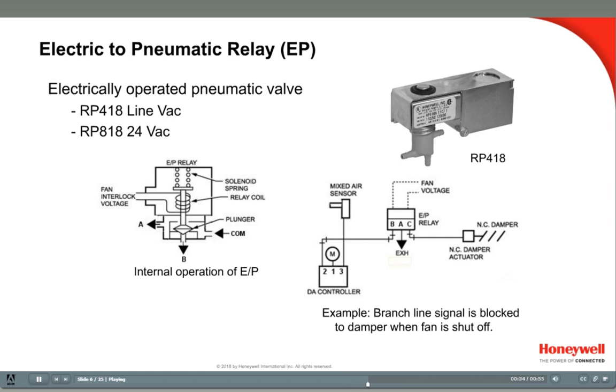The EP relay might be wired to a fan starter so that when the fan is on, the valve delivers air pressure to a damper. In this example, the damper will open when the fan is running and close when the fan shuts off. EPs can also be used as diverting valves, such as when dual PRVs are used, as seen in the Pneumatics 4 video on two-temperature thermostats.